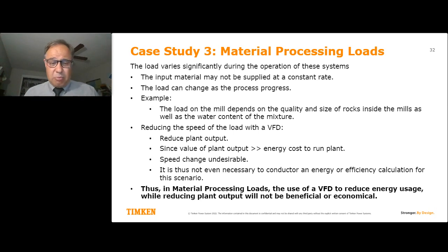That's why for a material processing load, I don't even need to do a calculation. The use of a VFD is not beneficial, as in it does not save me energy that would be anything close to more than the output than I lose.